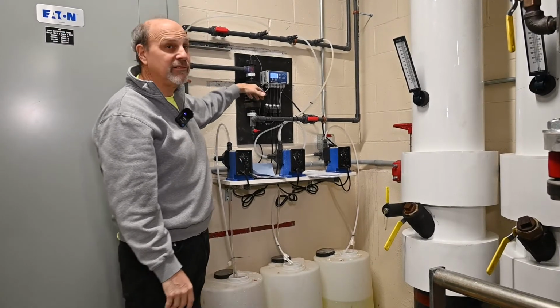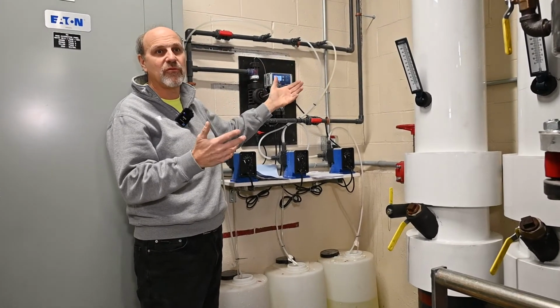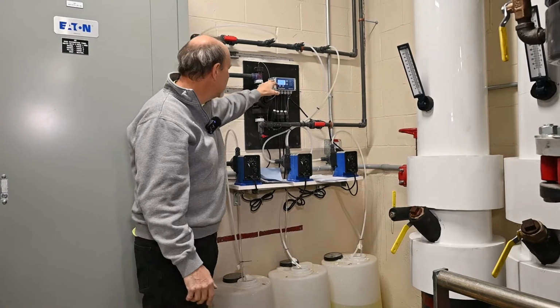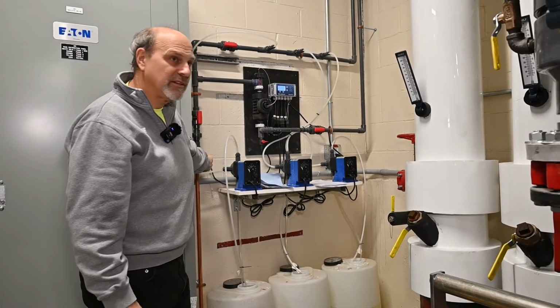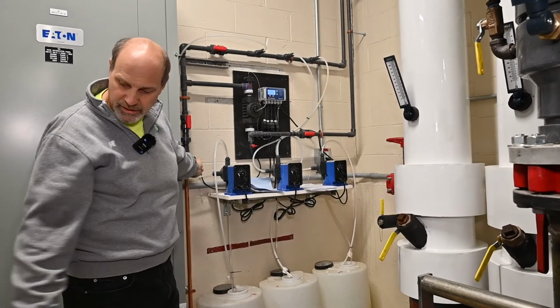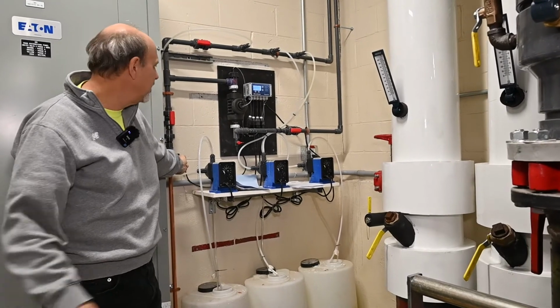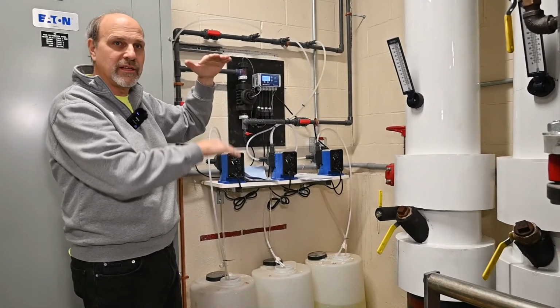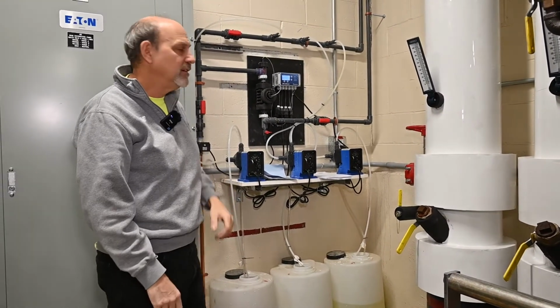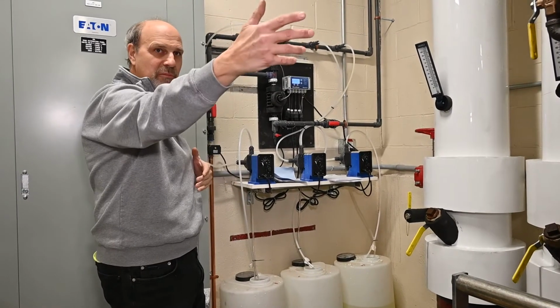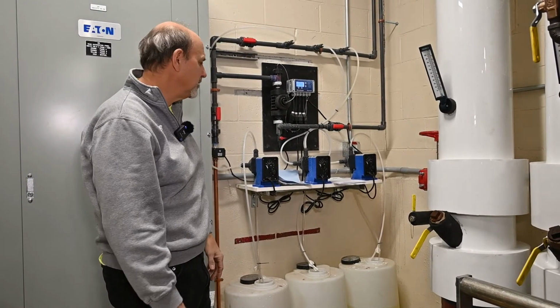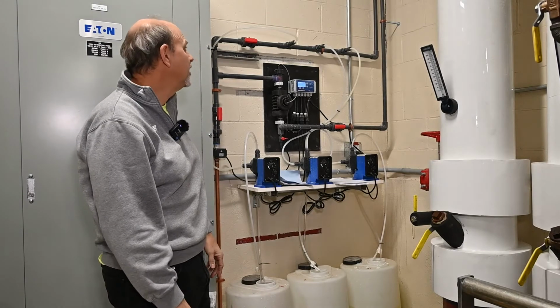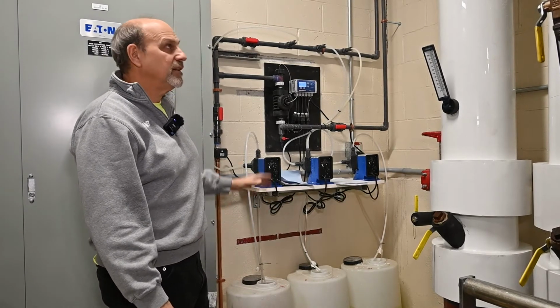Once the conductivity level gets too high, it's almost like a backwash that you're doing. This will sense it. It will energize this solenoid valve, and it'll bleed out water right to the sanitary drain here until that conductivity level comes down to an acceptable level. And then again, that's where the water makeup comes with the sump tank. So that's really the chemical system.